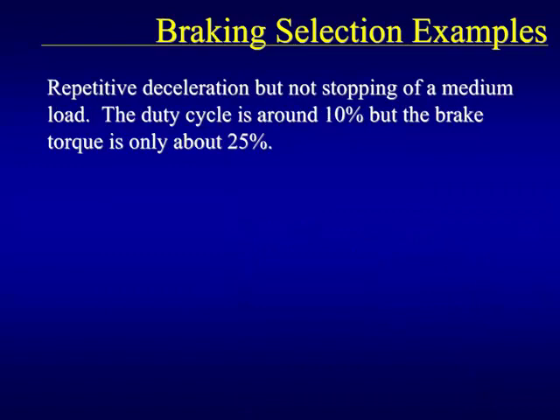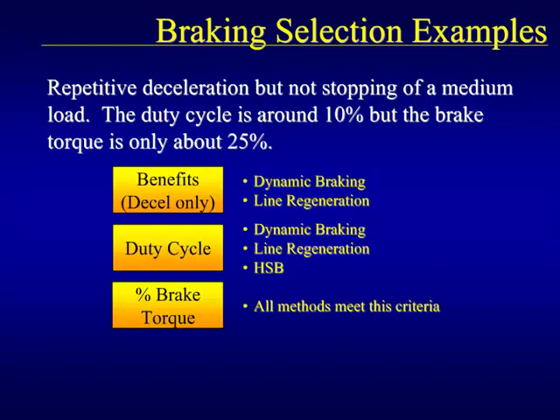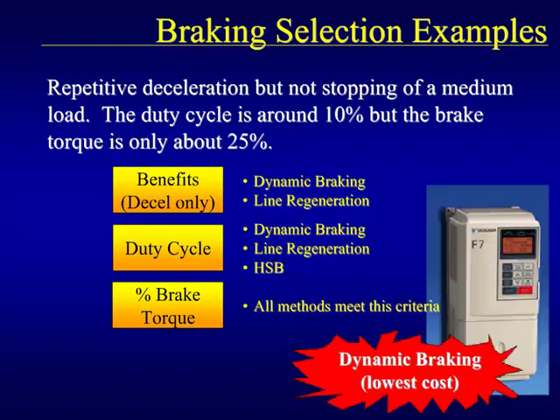Next, an application that has repetitive deceleration but not stopping of a medium load. The duty cycle is around 10%, but the brake torque is only about 25%. Because DC injection and high-slip braking are only used for complete stops, they are not viable options. Both dynamic braking and line regeneration meet the duty cycle requirements and all braking methods meet the braking torque requirements. Dynamic braking is most suitable for this application because it meets all necessary criteria but is less expensive than line regeneration.